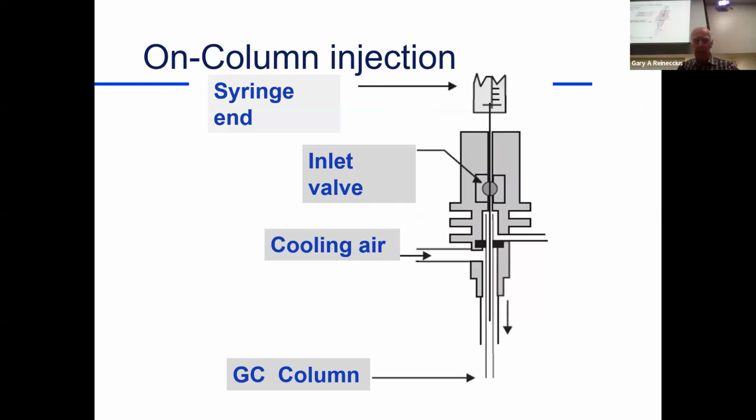This is the last one we'll look at. The first two are most common. So this is the last injection port, and really very, very different. Supposing you're working with chemicals or compounds that really aren't very thermally stable, and we don't want to inject them into 200 degrees centigrade and let them go poof. Okay, let's go ahead and use a much more gentle system.